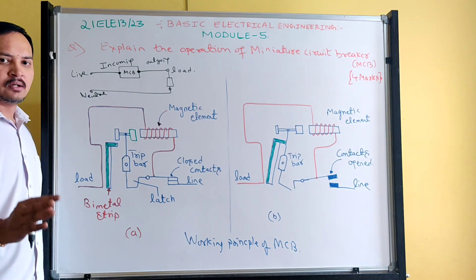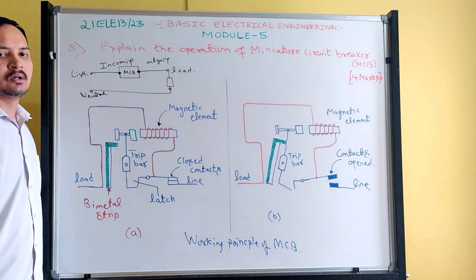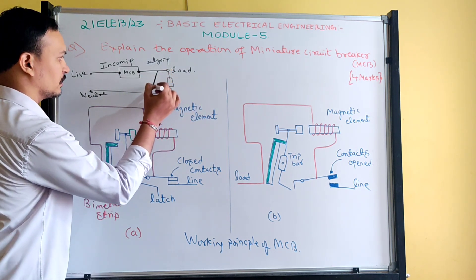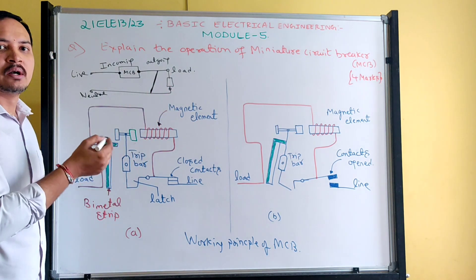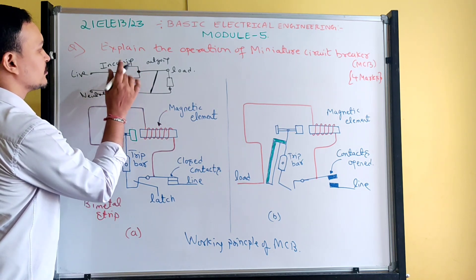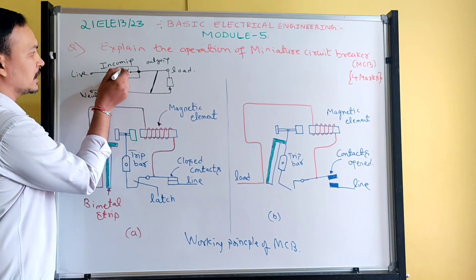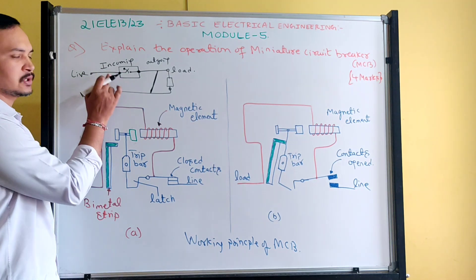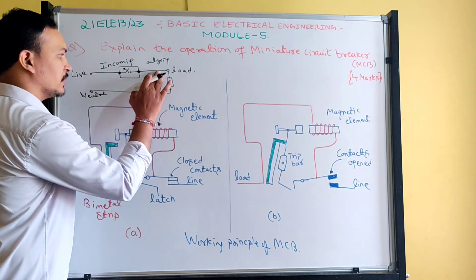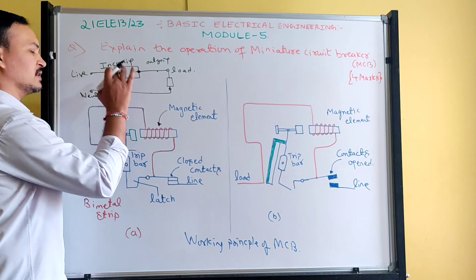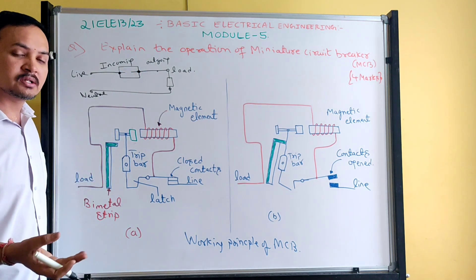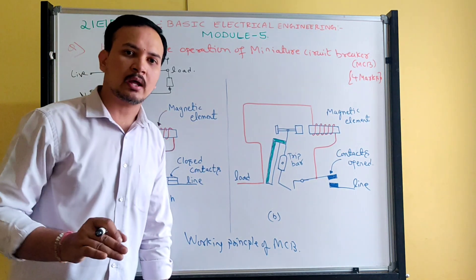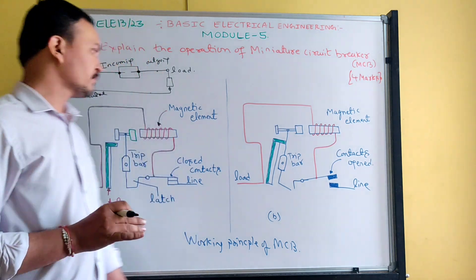We can analyze two conditions: one normal condition and another when a fault occurs. For example, when line and neutral is shorted — that is a short circuit — MCB is going to trip. The contacts will get open in the live wire. MCB also protects due to overload, when excess current flows due to overloading condition. MCB protects both overload as well as short circuit.